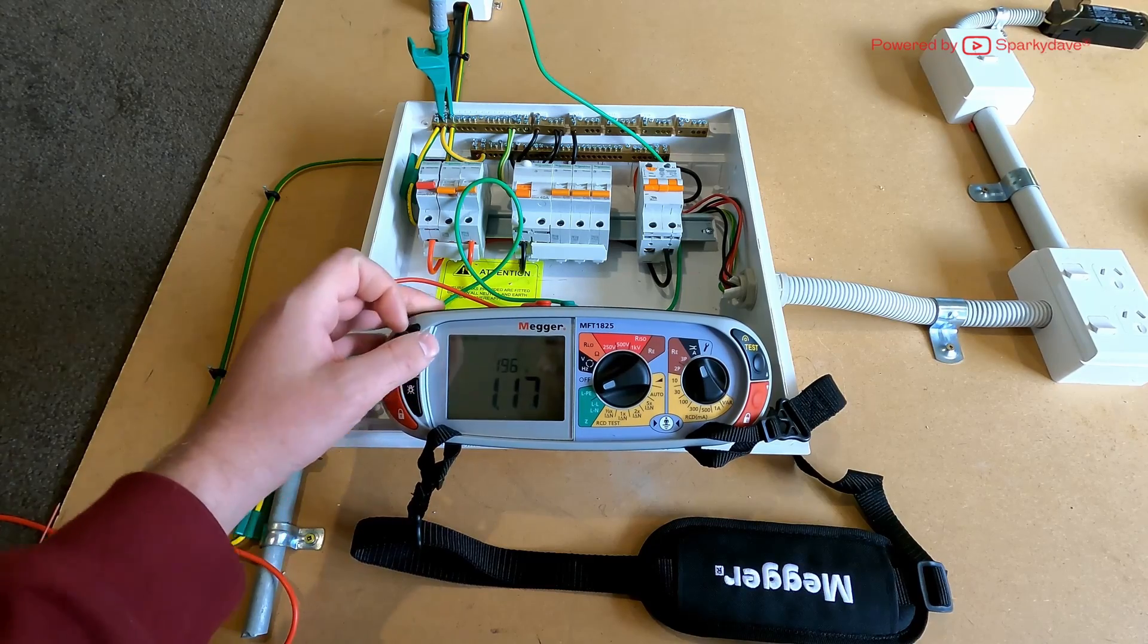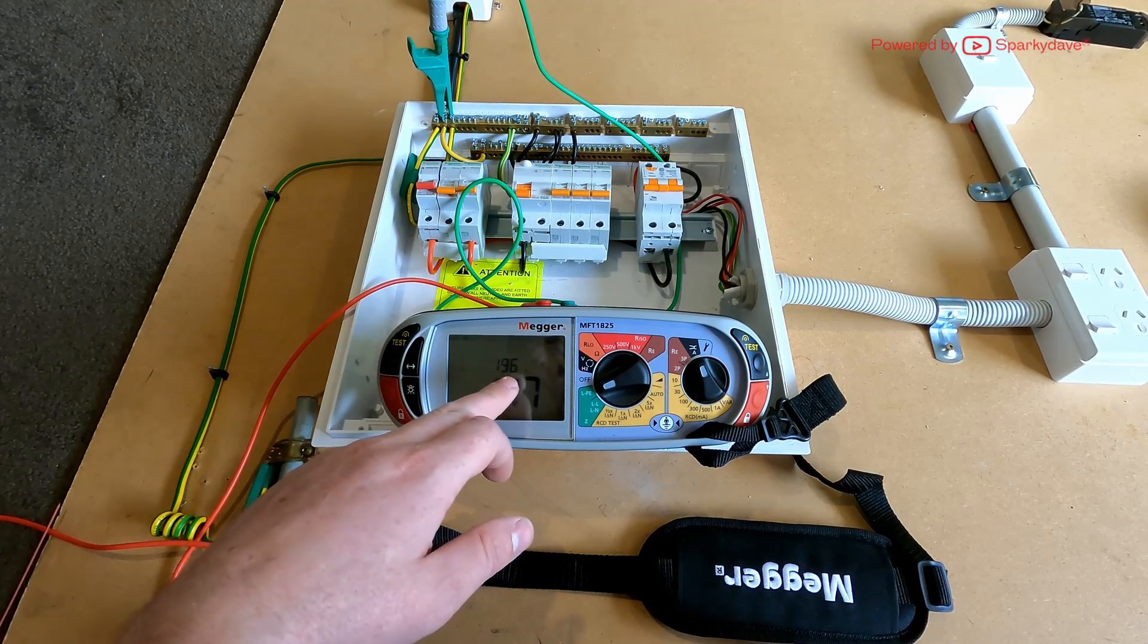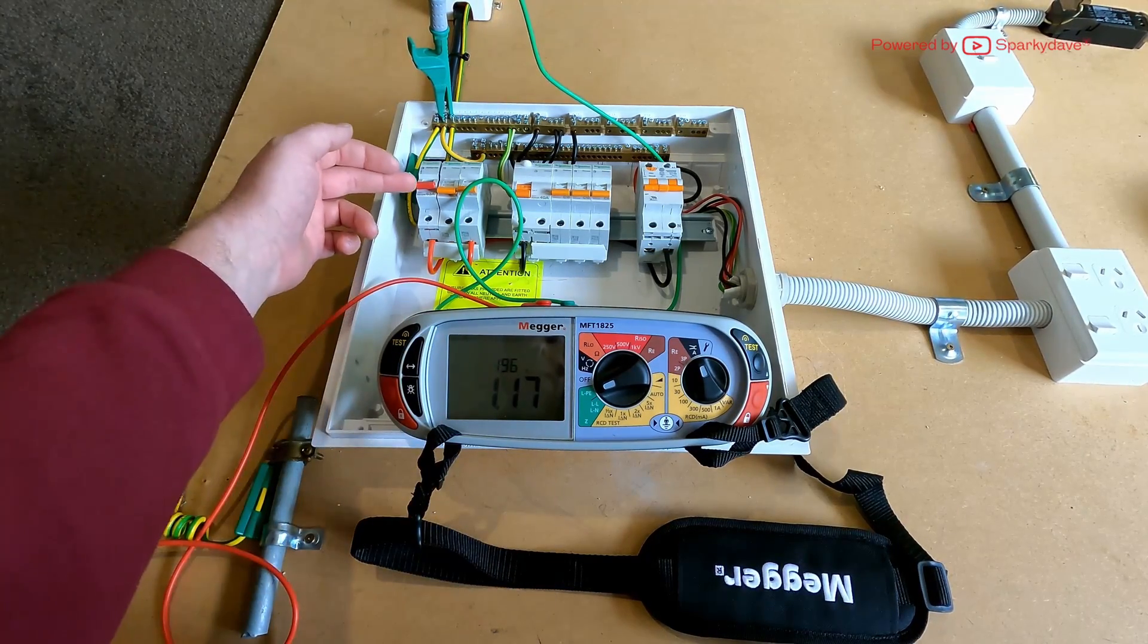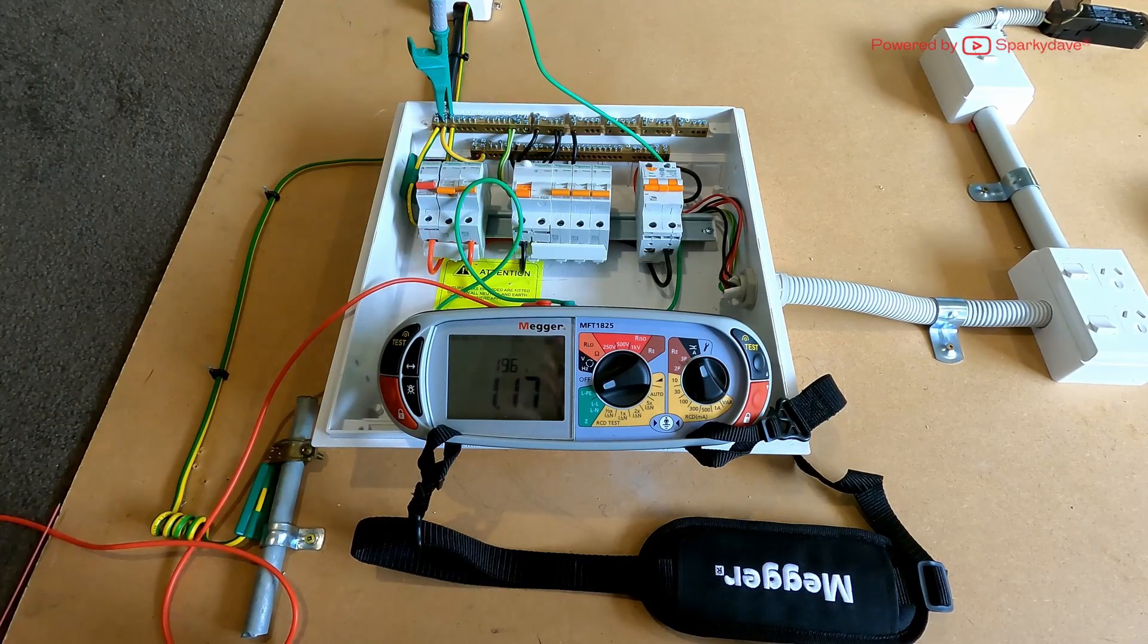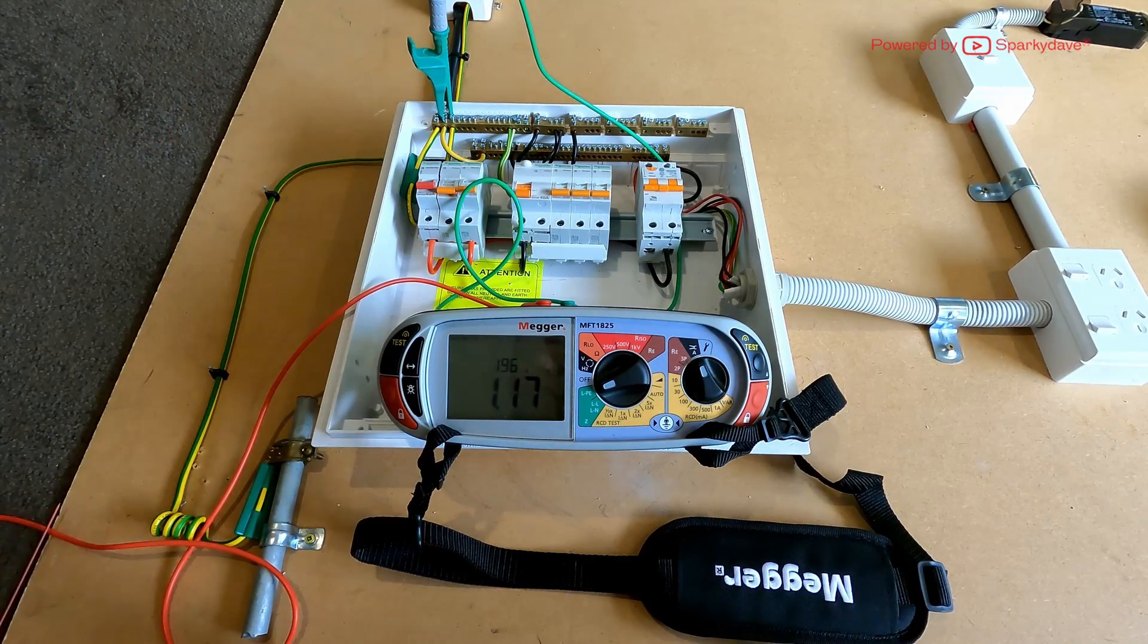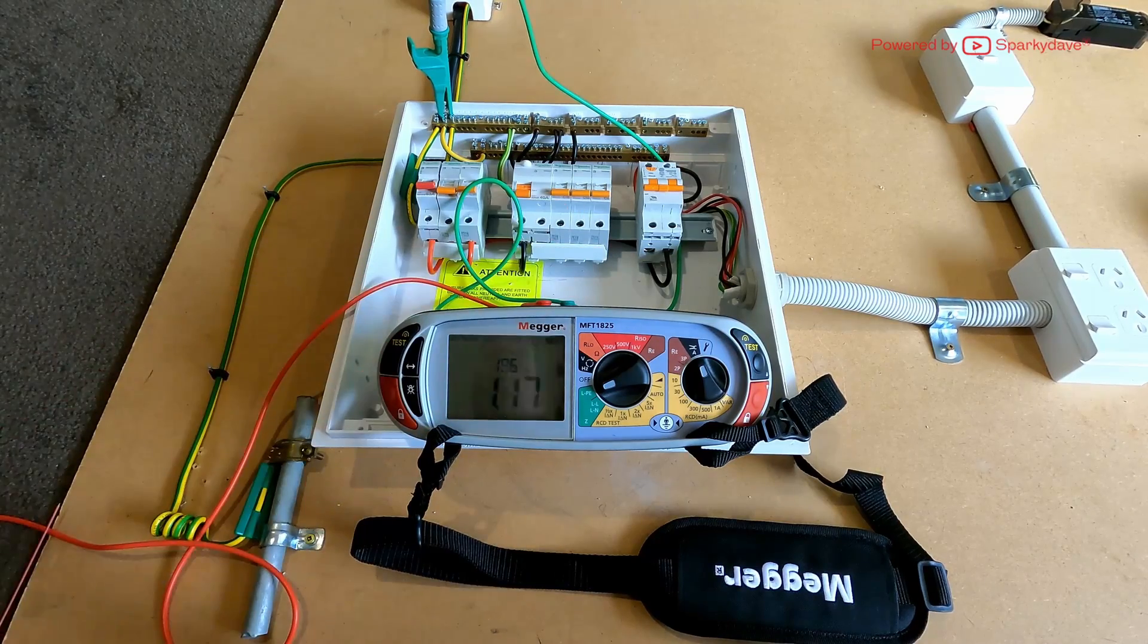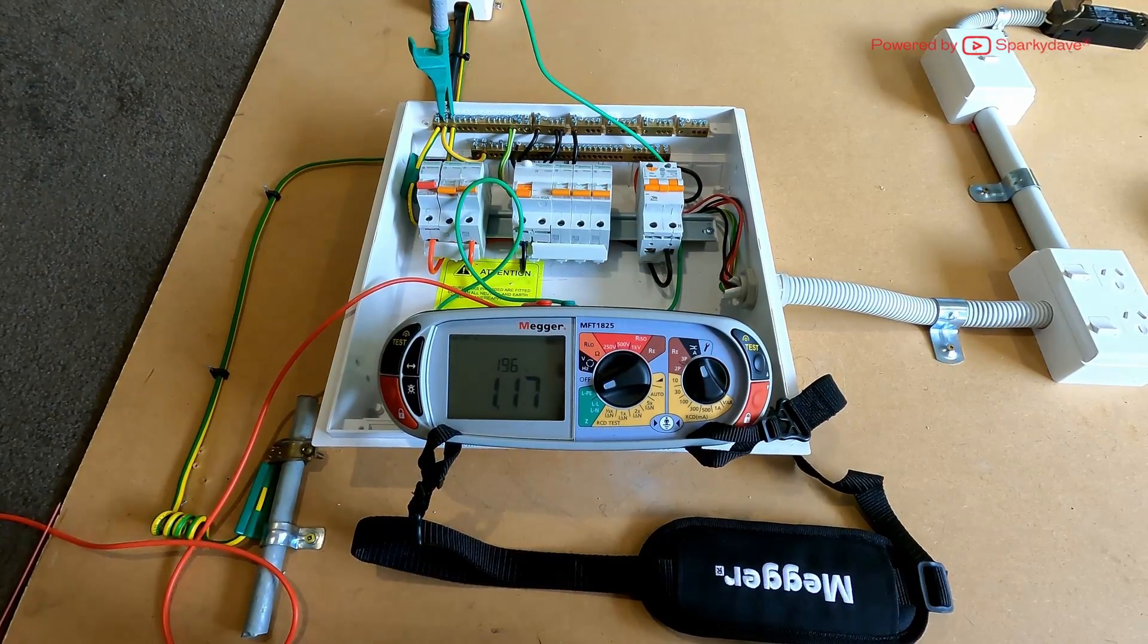This fault current produced is going to be high enough to trip the circuit protection. It's lower than that 6 kiloamp rating on the switchgear. Now with our impedance result, you want to go through and verify under table 8.1 whether or not your circuit protection is adequate to disconnect within 0.4 seconds.